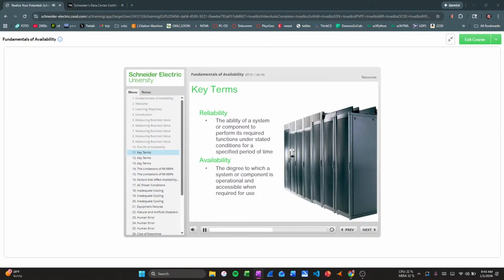Availability is determined by a system's reliability as well as its recovery time when a failure does occur. When systems have long, continuous operating times, failures are inevitable. Availability is often looked at because when a failure does occur, the critical variable now becomes how quickly the system can be recovered. In the data center, having a reliable system design is the most critical variable, but when a failure occurs, the most important consideration must be getting the IT equipment and business processes up and running as fast as possible to keep downtime to a minimum.